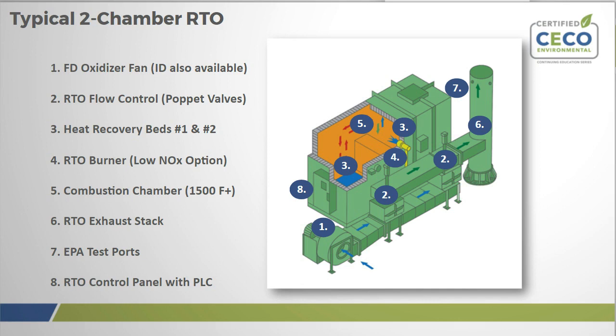So for a given cycle for the RTO, the inlet side media bed starts off very hot and is cooled down by the incoming process air. At the same time, the outlet media bed starts out cool and is heated by the air that just came through the combustion chamber. So the temps for the beds kind of act like a teeter-totter seesaw, where one bed cools, the other is heated. Once the beds are at their respective temperature extremes, a few hundred degrees apart, your flow control device, in the case of this image, number 2 here, a poppet valve mechanism, will switch and reverse flow through the whole system, and the process starts all over again. And then your outlet bed becomes your inlet bed, which is hot, and your process absorbs heat from that. So this results in really extremely high thermal recovery.